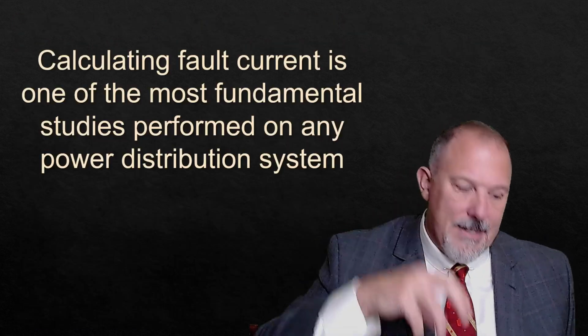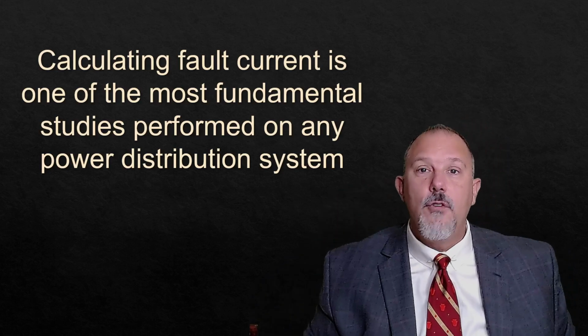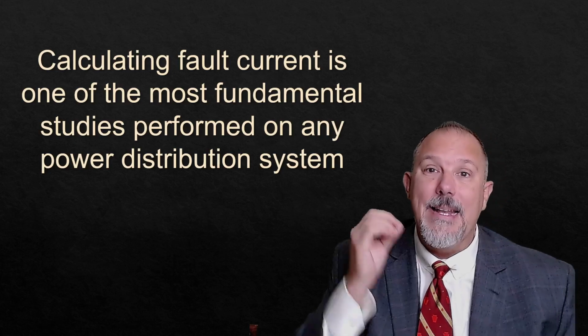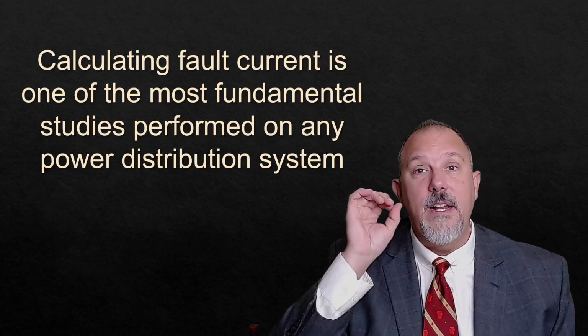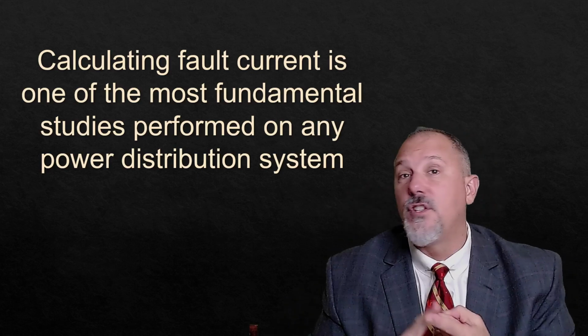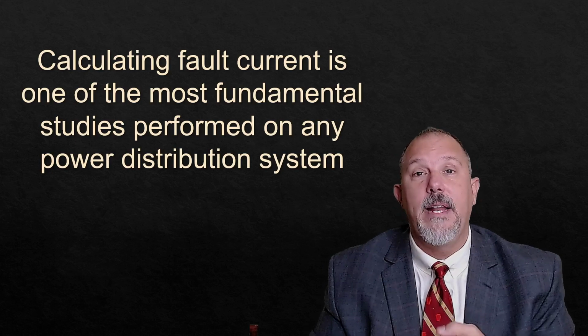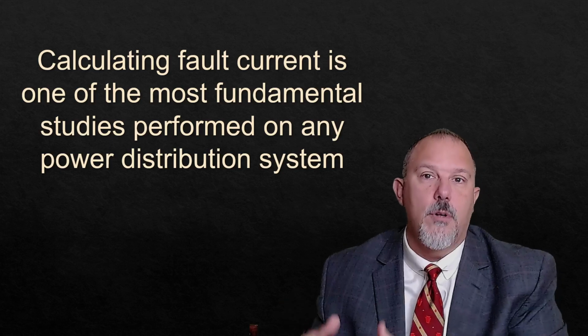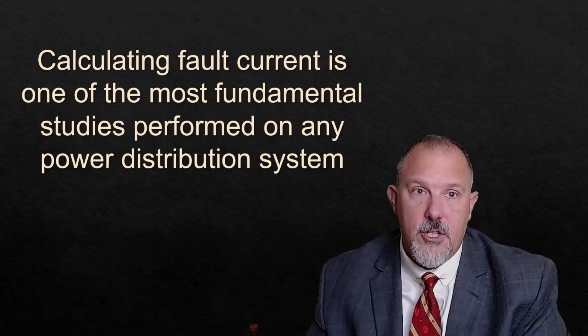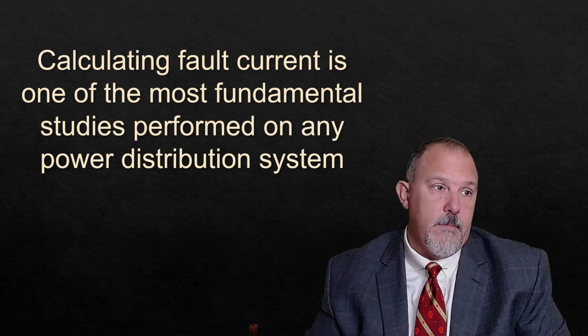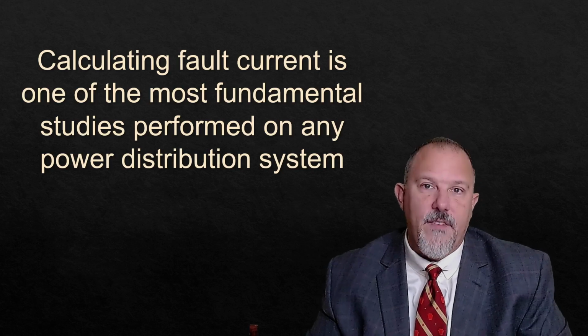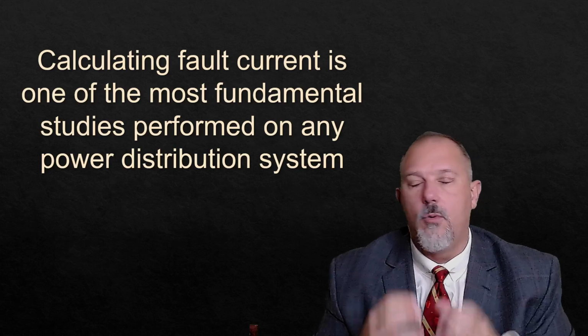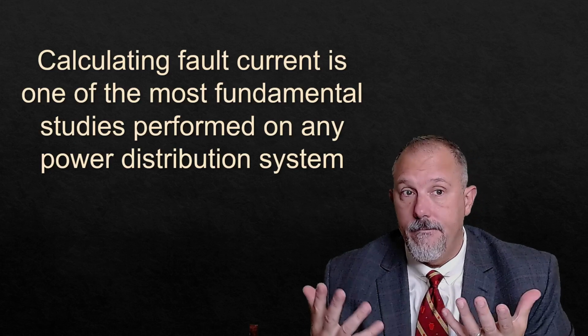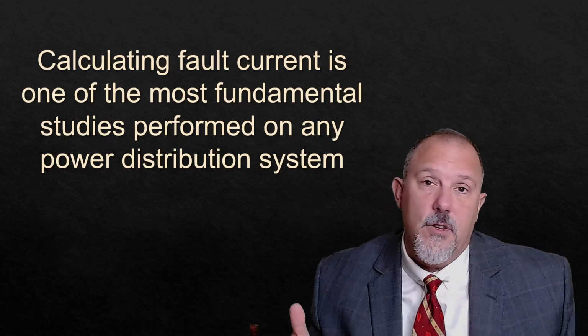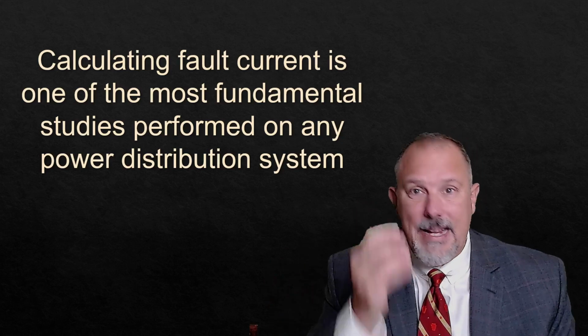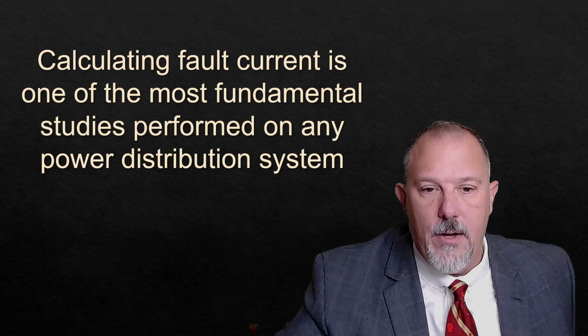So calculating that fault current is one of the most fundamental studies. And if you're doing nothing else with that data, you at least have to make sure that all of the products are rated to handle that current, either an interrupting rating if it's a fuse or a circuit breaker, or a short circuit current rating if it is a piece of equipment like a busway, panelboards, switchgear, conductors, receptacles, anything that is going to deliver the current. You want it to hold together and not explode. Or if it doesn't explode, you could pull the conductors out, or just damage it enough that eventually it will fail miserably.